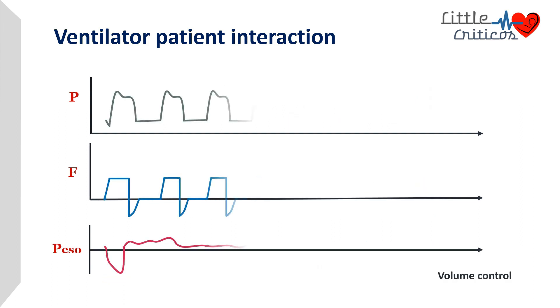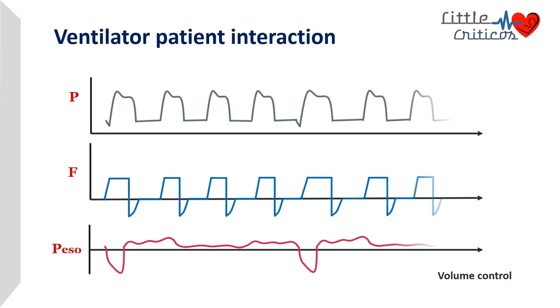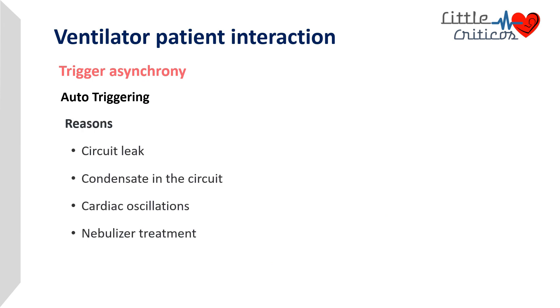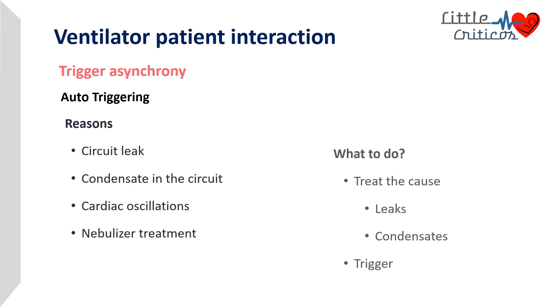A similar finding can be observed in volume-controlled mode of ventilation. Auto-triggering commonly occurs due to a circuit leak, condensate in the circuit, cardiac oscillations, and during nebulizer treatment. It is important to identify the cause — whether leak or condensate — and correct it. Sometimes, inappropriate trigger settings may also lead to auto-triggering, which may require an increase in trigger setting.